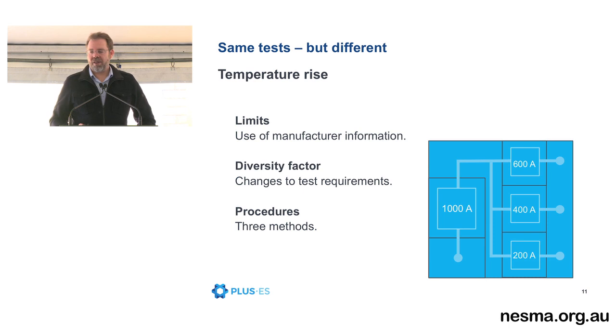Also, the test methods. By far the most popular test method is, well, minimise the number of tests. Depending on how you arrange the incoming unit and the outgoing units, we can do a single test and verify the rating for the incomer and the outgoing functional units. However, there's also the opportunity to verify everything individually, so by components. That would be the second test method. And the third one takes it to another level. You've got by components, but also now you can rate bus bars. So you can rate a horizontal bus bar for a certain current rating, and vertical bars even if you wish. So they have added these extra ratings that you can now apply.